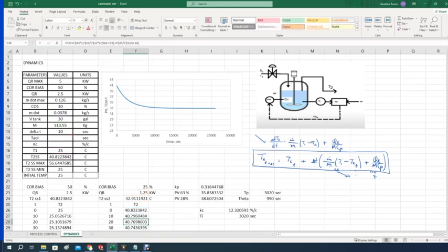Enter. Now if you run that, eventually it will start to cool down to this new temperature, 32.91. Excellent. So what we are basically saying is that we know the two temperatures, the initial temperature and the final temperature for this process, and we are going from 50 to 25. So we know the controller bias, how the percentage is changing, and with that we can calculate the Kp value. The Kp value, as shown there, is the difference between this temperature minus this, over this controller bias F22 minus this one here that is 50.